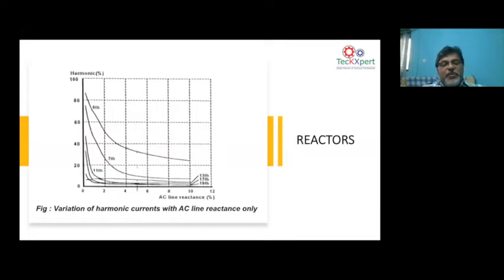That means when you put a line reactor at the input of the drive, you are ensuring the harmonics injected by the drive are reduced, depending on the size of the line reactor. But you cannot go and put a 5% or a 6% line reactor just for reducing the harmonics, because ultimately the line reactor causes a voltage drop. And finally, if your VFD has to run a motor, you cannot put a big line reactor. Sometimes it will affect the speed-torque characteristics of the drive. So you should carefully select the input line reactors. Going to the next slide.